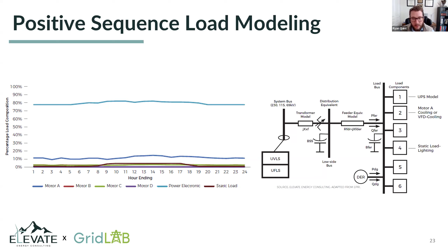For those that don't work in the modeling and studies phase, we've got basic power flow studies - basic because the models are rather straightforward and easy to use. These represent the injections and withdrawals of megawatts onto the system. You've got generators modeled, transmission system models, loads modeled. When you're adding in these large loads, you're identifying network upgrades, running contingency analysis, and saying, I want to connect this large load, but to do so I'm overloading these 3 lines or components or this transformer. I've got congestion in these areas, and voltage problems that need to be fixed.